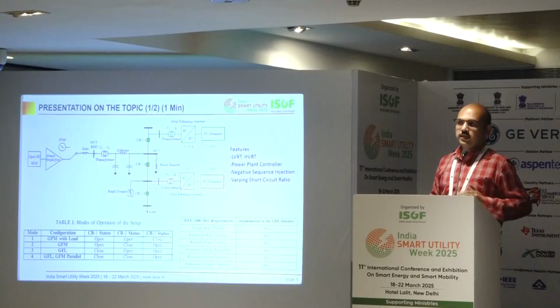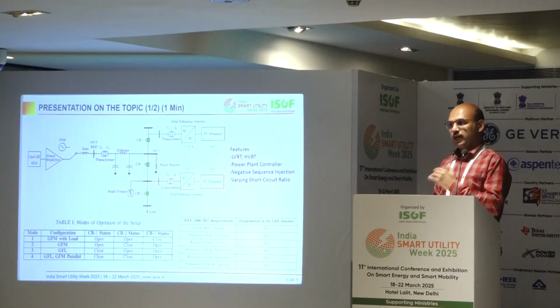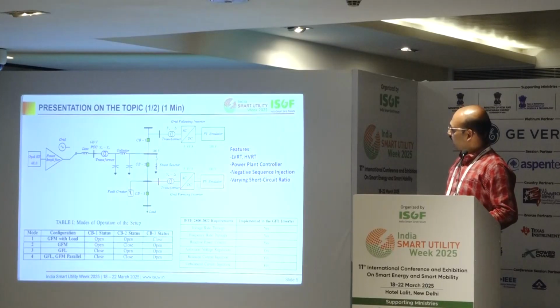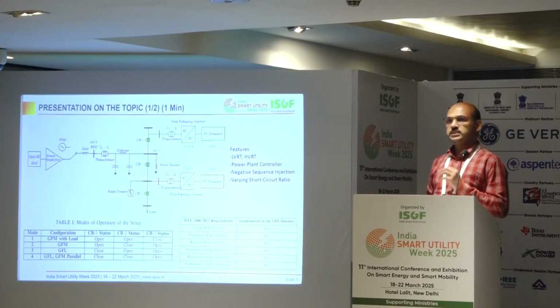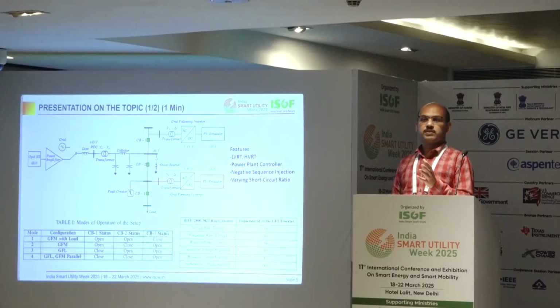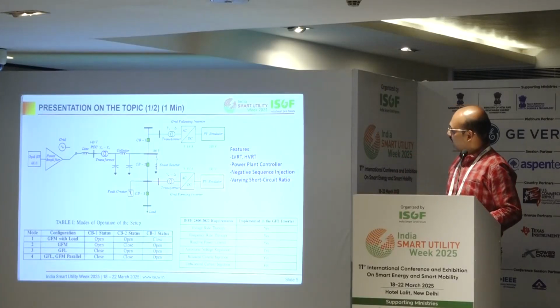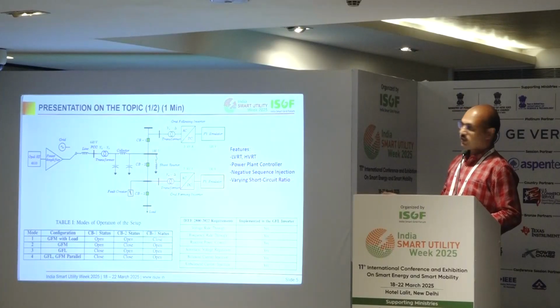Currently we have a parallel combination of grid following and grid forming inverters. We have a PV emulator which emulates the IV characteristics of PV panels, so PV panels are emulated through this PV emulator. The output of this goes to, in this case, a grid forming inverter of 3 kVA, and this is the grid following inverter, also 3 kVA.